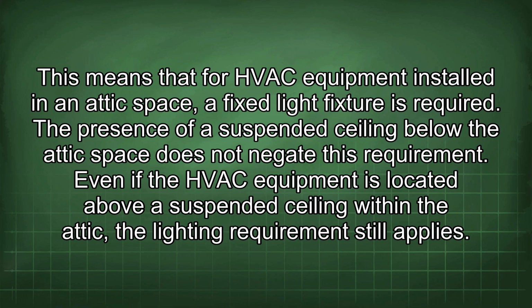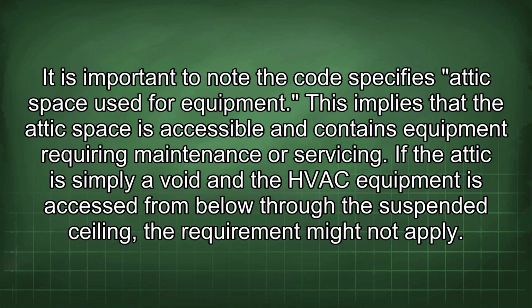The presence of a suspended ceiling below the attic space does not negate this requirement. Even if the HVAC equipment is located above a suspended ceiling within the attic, the lighting requirement still applies. It is important to note the code specifies attic space used for equipment. This implies that the attic space is accessible and contains equipment requiring maintenance or servicing.